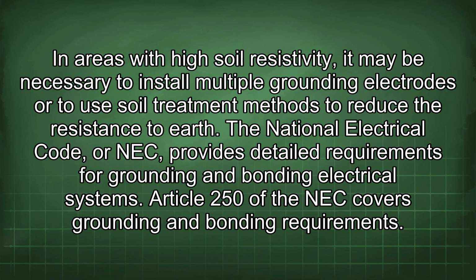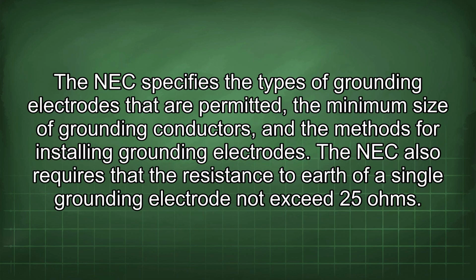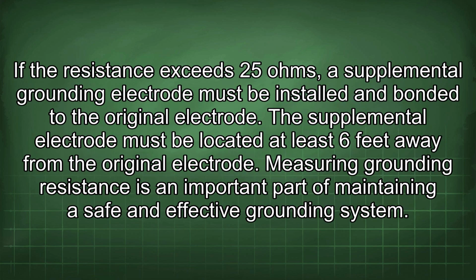The National Electrical Code, or NEC, provides detailed requirements for grounding and bonding electrical systems. Article 250 of the NEC covers grounding and bonding requirements. The NEC specifies the types of grounding electrodes that are permitted, the minimum size of grounding conductors, and the methods for installing grounding electrodes. The NEC also requires that the resistance to earth of a single grounding electrode not exceed 25 ohms. If the resistance exceeds 25 ohms, a supplemental grounding electrode must be installed and bonded to the original electrode. The supplemental electrode must be located at least 6 feet away from the original electrode.